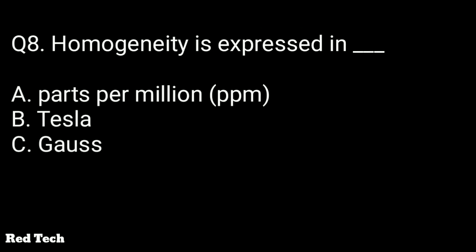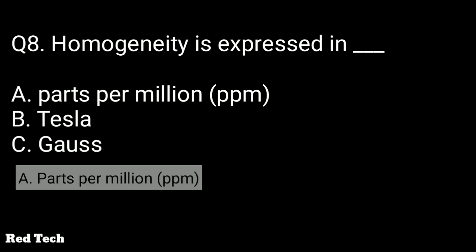Question number eight: MRI homogeneity is expressed in — the options are parts per million, tesla, or gauss. The right answer is parts per million. Tesla is the unit of magnetic field strength and is the bigger unit, while gauss is the smaller one.